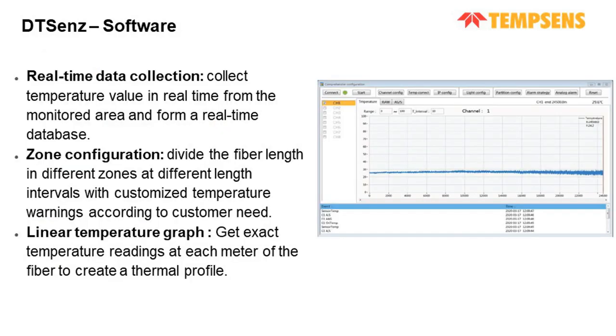This is the software screen. Distributed temperature systems are designed to deliver high resolution, real-time thermal monitoring over extended lengths of optical fiber. One of the core functionalities of a DTS system is real-time data acquisition, wherein temperature measurements are continuously recorded along the entire length of the fiber. These readings are processed and stored in a dynamic database, enabling operators to access time-stamped thermal data for immediate analysis. So the data for the whole cable is recorded in real time, and thus it enables the operators to access them.